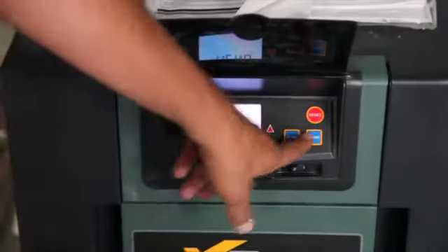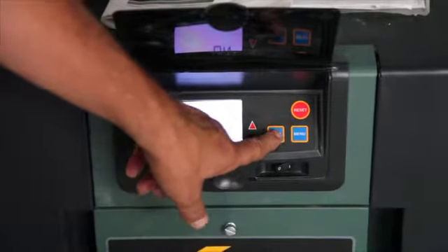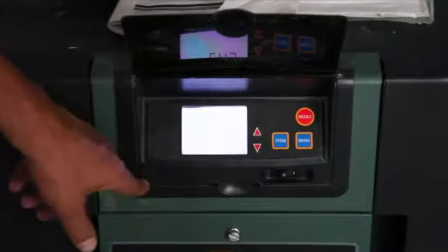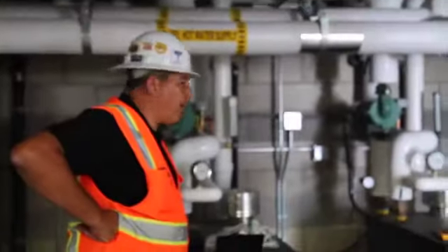So in the menu screen, there is an adjust. And we can turn this boiler back on once we take care of its own internal problem. If it does fail, it'll run the lag boiler via the communication. It won't do it automatically? It won't switch over? It will. It'll see this one's failed. If it is failed, it'll run the lag boiler. That's correct. Even if you turn this switch off, it'll run the lag boiler.